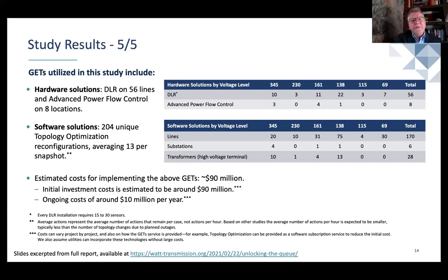In terms of topology optimizations and reconfigurations, we identified 204 unique topology optimization reconfigurations across these 24 models extrapolated. The majority of switching operations are again at the 138 kV level, with the next tier at 161, followed by 69 kV. We looked at optimization solutions all the way down to 69 kV, and it's important to know that when we did the SCOPF, the security constrained power flow, we wanted to maintain reliability standards at 69 kV and up within SPP, as well as 100 kV and up in adjacent systems.